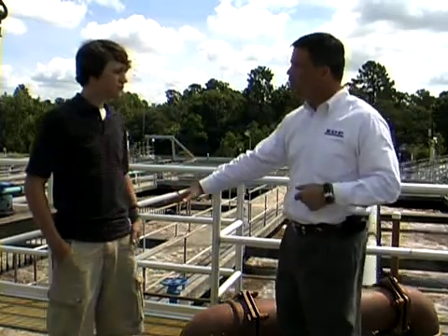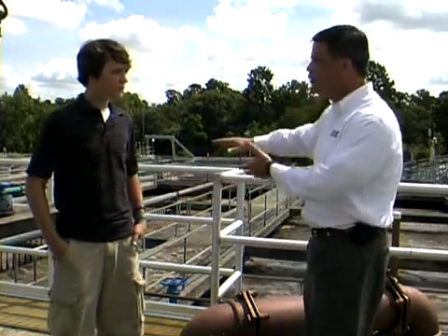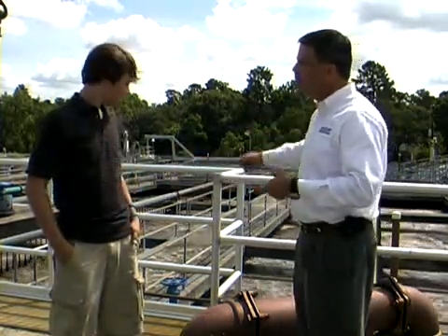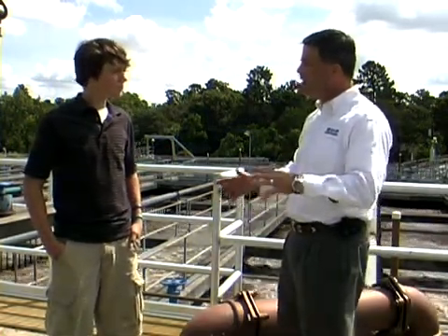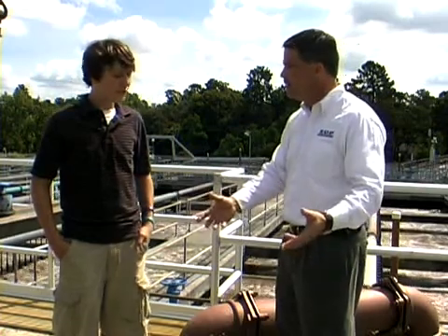So the wastewater is entering here at the headworks. Then it flows over to these chambers here. We mix it with bacteria. Now we grow certain kinds of bacteria that like what's in my wastewater. Well, the wastewater has the dissolved organics in it. The bacteria use those dissolved organics as an energy source. They grow more bacteria. So essentially what we've got going here is a bacteria factory. We use the bacteria to remove the organics.